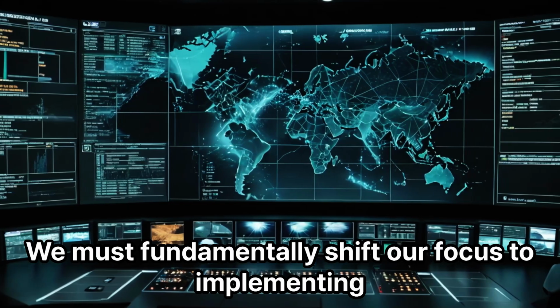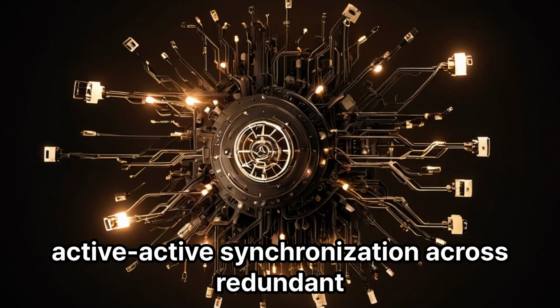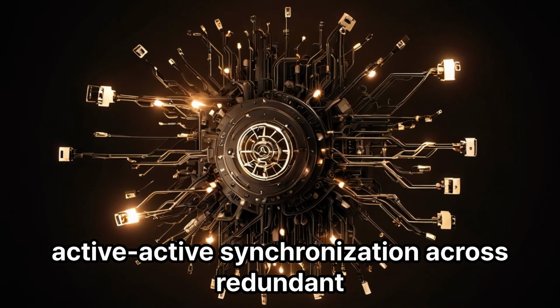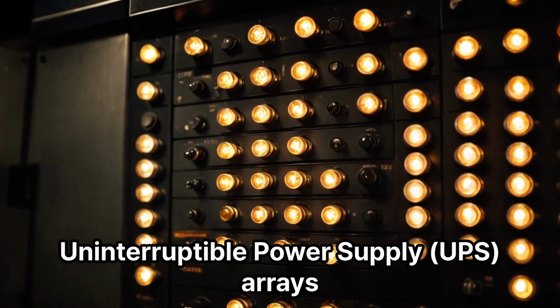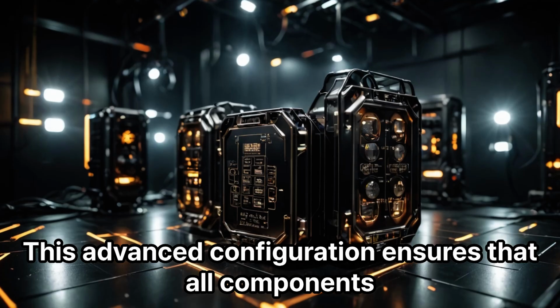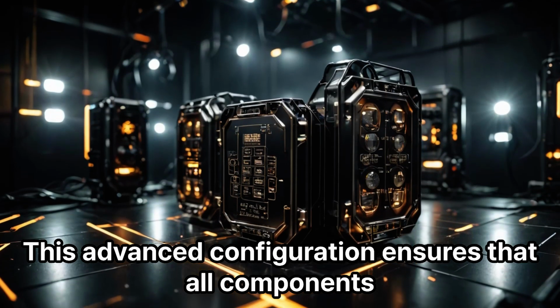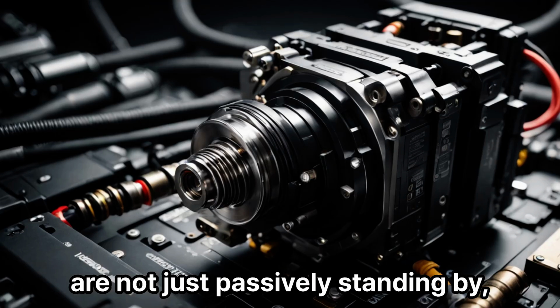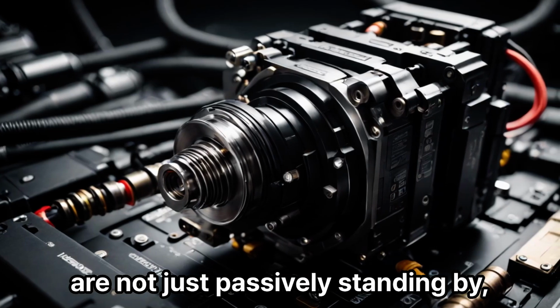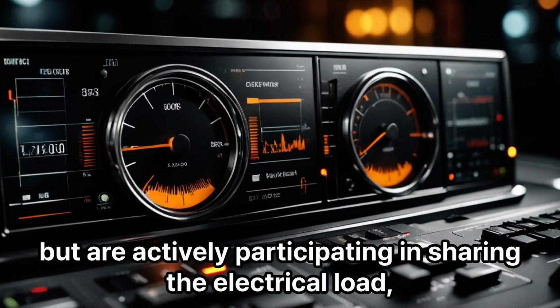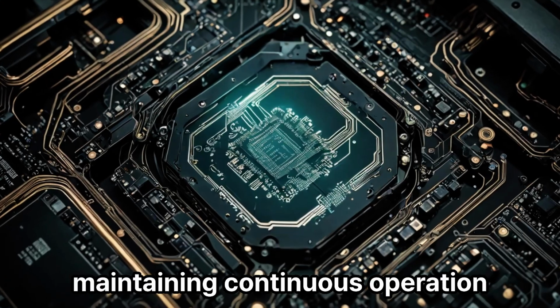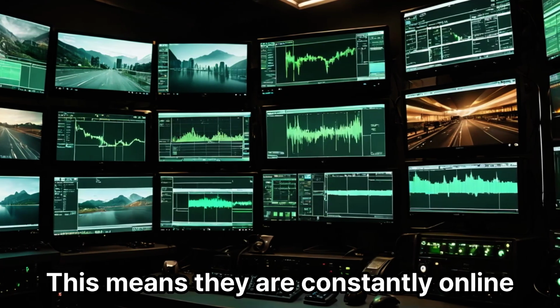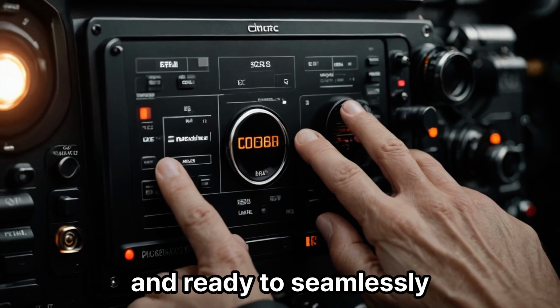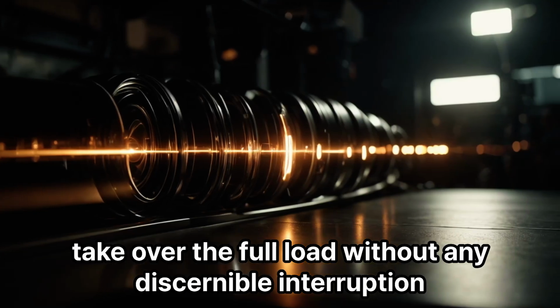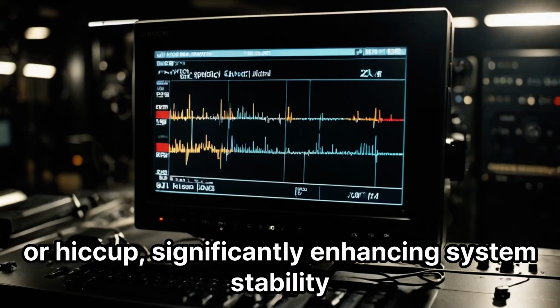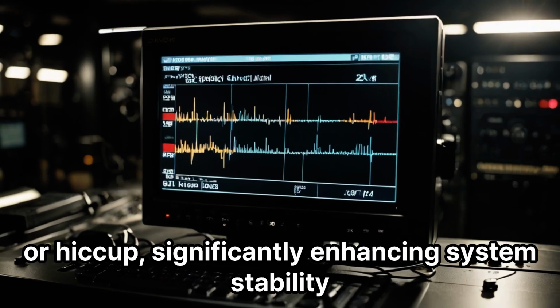We must fundamentally shift our focus to implementing active-active synchronization across redundant, uninterruptible power supply (UPS) arrays. This advanced configuration ensures that all components within the redundant system are not just passively standing by, but are actively participating in sharing the electrical load, maintaining continuous operation. This means they are constantly online and ready to seamlessly take over the full load without any discernible interruption or hiccup, significantly enhancing system stability.